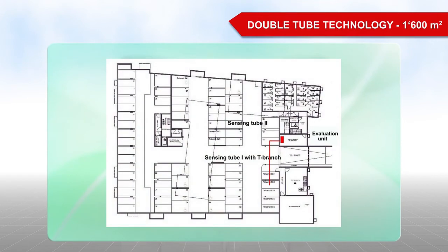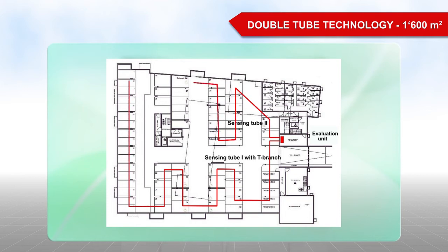Two sensing tubes can be connected to the SecuriSens ADW 535, which is known as double-tube technology. This means that an area of up to 1,600 square meters can be monitored with one evaluation unit.